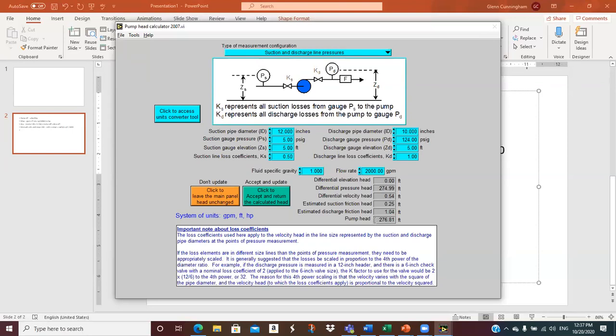Wow, that's pretty nice. Now, you will get an opportunity to do all of this by hand. After you do this by hand a couple of times, you really appreciate this calculator, because it's not terribly difficult. It's all fundamentals, but it's probably going to take you 15 minutes to calculate that pump head. When all you have to do is stick numbers in here, you get it in about 20 seconds. It's real handy. Then it breaks it down into the different components that go into the total pump head.